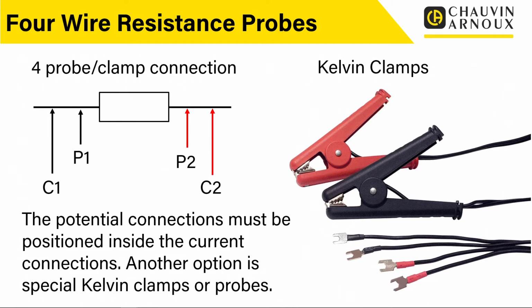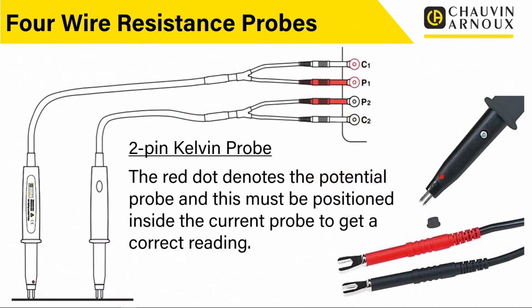So Kelvin clamps, or the 2-wire type clamp. Sometimes people get confused because they look at them and just think it's a normal croc clip, but actually you've got 2 wires going in there and each jaw is wired up separately. Now we can also get these Kelvin type probes, and there are a lot of different versions of these, different sizes, different shapes. But the fundamental part is that you've got 2 probes in the end, and these are generally spring-loaded probes, so when you push them on, they'll fit around any surface imperfections or any movement of your hand position.